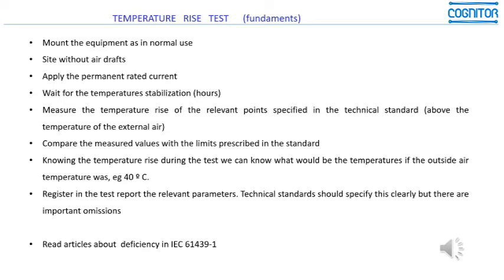In the case, for example, of power transformers, even if it's a very big transformer, this can be more than days. We can have 2 days, 1 day, waiting for the temperature stabilization. For switchgear, like isolators and circuit breakers, this usually takes some 4, 5, 6 hours, not such a very big duration.